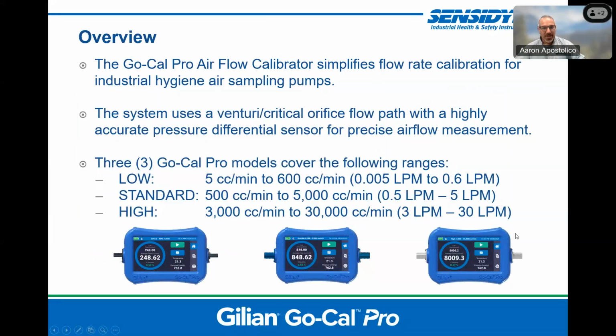Back to our presentation. So as you saw in the video, the Go-Cal Pro is really designed to simplify flow rate calibration of your industrial hygiene air sampling pumps. The system uses a technology made up of venturi and critical orifice, which creates a very stable flow path that goes through very accurate pressure differential sensors to measure that precise airflow.